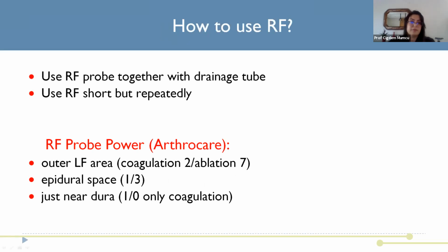How to use RF? Use the RF probe together with the drainage tube. It's important. And use RF short but repeatedly. RF probe power should be set at the outer ligamentum flavum area: coagulation should be 2, ablation is 7. On the epidural space, coagulation should be 1, ablation is 3.